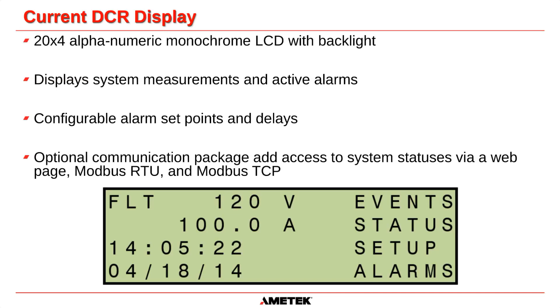The current DCR display uses a 20 character by 4 line alphanumeric monochrome LCD with a backlight. This LCD does not have a touchscreen, so you have to use the membrane switch buttons to navigate through the screens. It displays the system measurements and any active alarms that are on the system. The customers can go in and adjust alarm set points and delays as they see fit using the LCD screen. And we have an optional communications package that allows the system to be accessed, and you can see the status via a web page. And we also talk Modbus RTU and Modbus TCP.